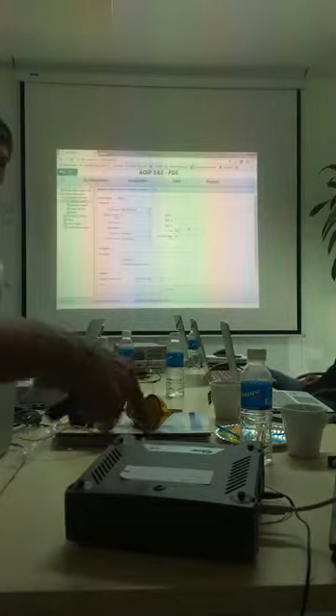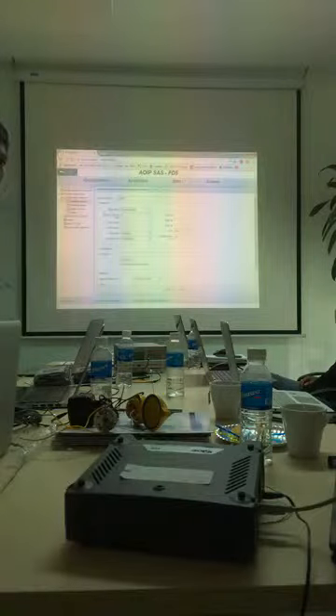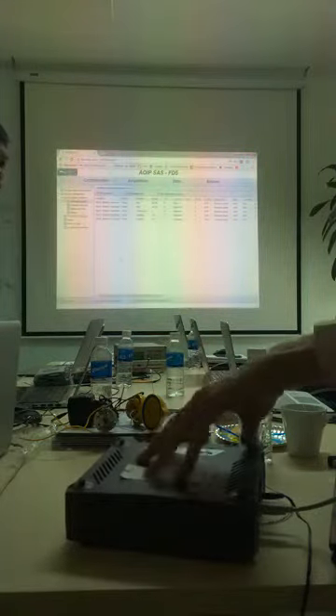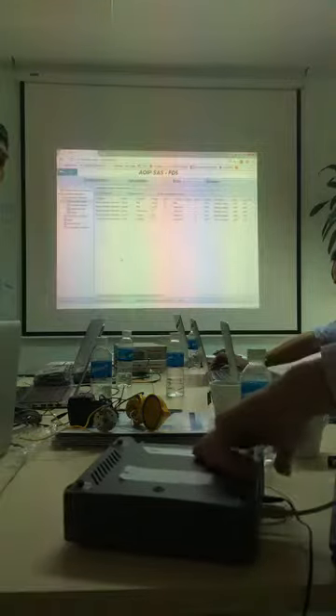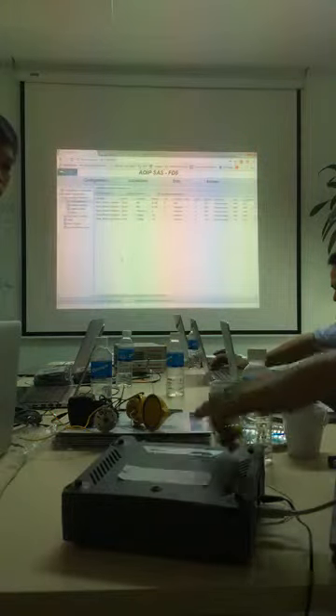What is the difference between the slave and master configuration? Same. If you go there, I have only 5 channels. Yeah. Then your customer has 5 channels. He says, I want 10 additional channels. I cannot modify this one. But he can purchase a slave module of 5 channels. He will put another box that looks exactly the same on the top, and he will connect it to this one.